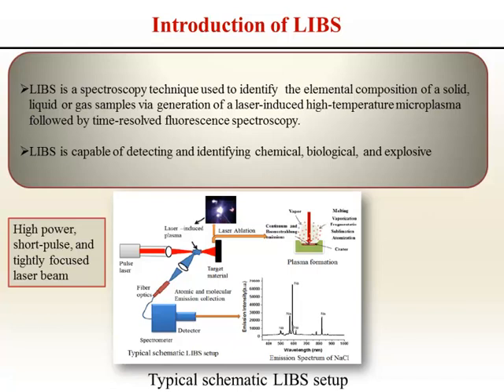The plasma emits light, and the light contains information of the atomic and molecular emission signatures of the target material. The light is then collected by a fiber optic or CCD camera, which is connected to a spectrometer. The spectrometer resolves the atomic and molecular peaks into their respective wavelength peaks. The example you see here is the emission spectra from a sodium chloride crystal. This tells us the atomic peak with respect to the neutral sodium atom from that material. In this wavelength region, it is very difficult to detect the anions attached to the sodium compound.